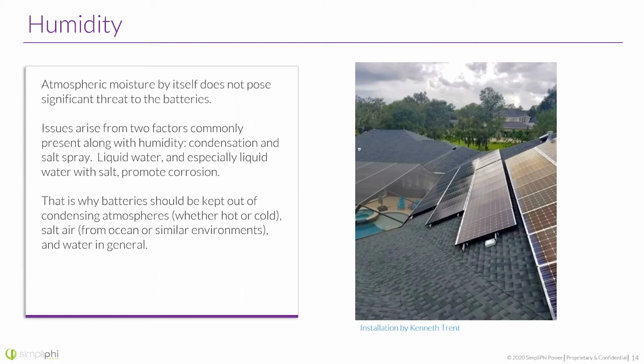It would be pretty rare that you would see a lot of that, as long as you were installing indoors as you're supposed to. You really should not end up with that much or any salt spray. And as far as humidity goes, kind of same thing. You shouldn't expect that in, let's say, a well-insulated area the battery's installed in. You really aren't going to see a lot of that liquid water drip. So again, that's why it should be kept out of condensing atmospheres. So hot or cold, salt air from the ocean or similar environments, and water in general.